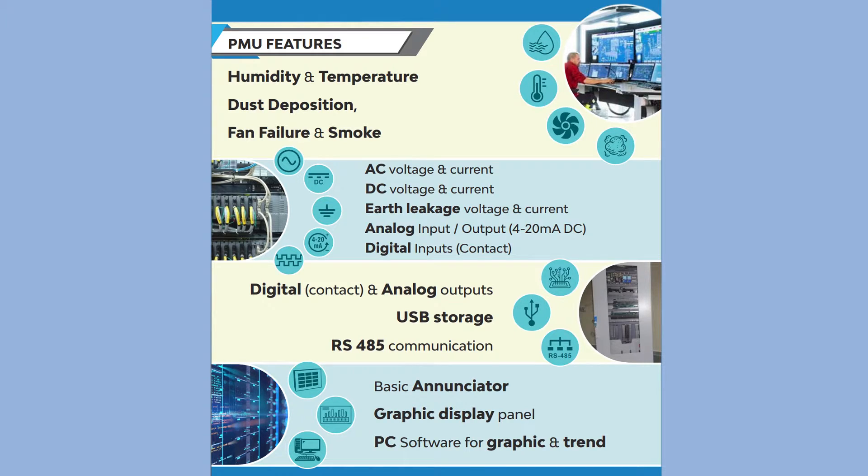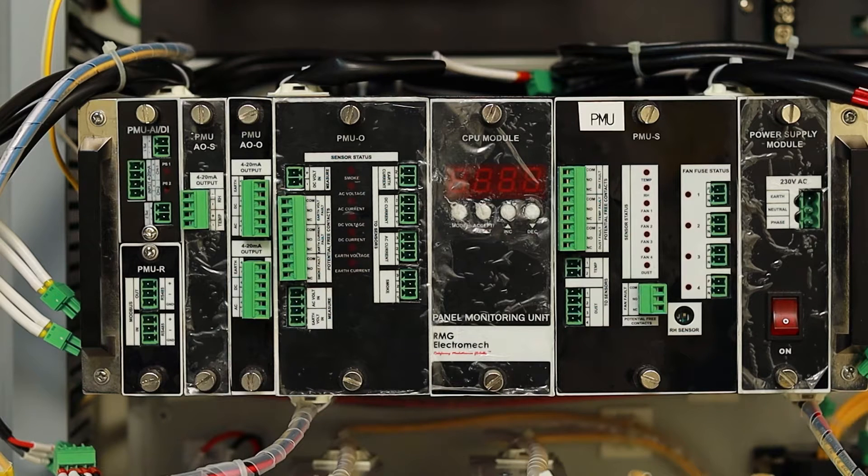Let us now check out the parameters that are monitored. These are: temperature, humidity, dust deposition, fan running status, smoke, AC current and voltage, DC current and voltage, earth current and voltage, 24V DC redundancy failure, and corrosion with third-party sensor. Let us now see what the PMU consists of.